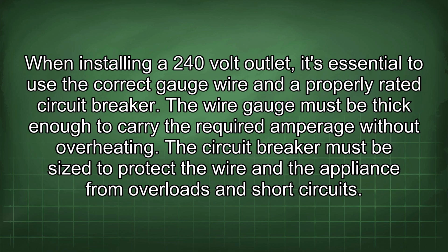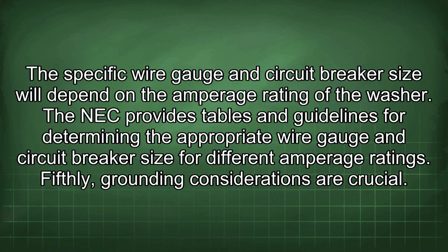Fourthly, the proper wiring and circuit breaker selection. When installing a 240 volt outlet, it's essential to use the correct gauge wire and a properly rated circuit breaker. The wire gauge must be thick enough to carry the required amperage without overheating. The circuit breaker must be sized to protect the wire and the appliance from overloads and short circuits. The specific wire gauge and circuit breaker size will depend on the amperage rating of the washer. The NEC provides tables and guidelines for determining the appropriate wire gauge and circuit breaker size for different amperage ratings.